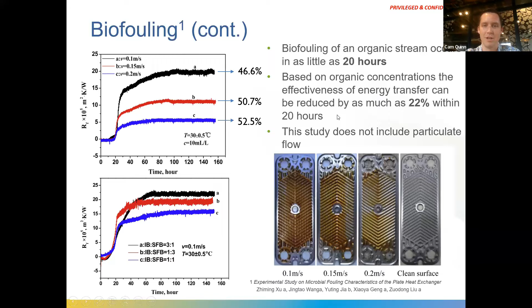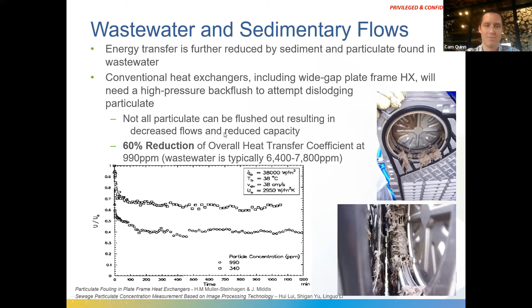Then we also have wastewater and sedimentary flows. On top of the biofilm that can grow on your heat transfer surface, we have to deal with the sediment and particulate in the wastewater flowing through the heat exchangers, which settles out in the nooks and crannies, again impacting heat transfer efficiency. Conventional heat exchangers, including wide gap plate frame heat exchangers, will need high pressure back flushes to dislodge all this particulate, and you don't always get back to 100% on a back flush. So you're again looking at costly maintenance on these heat exchangers.